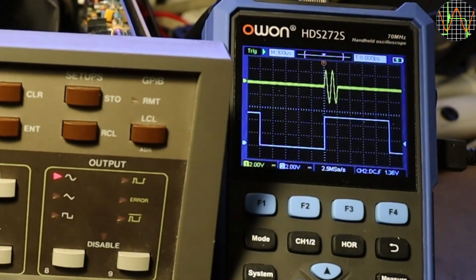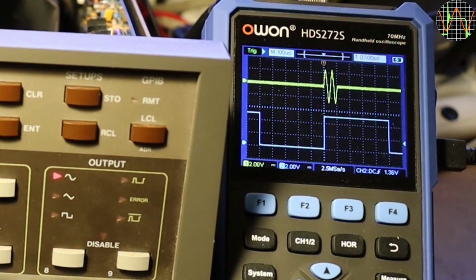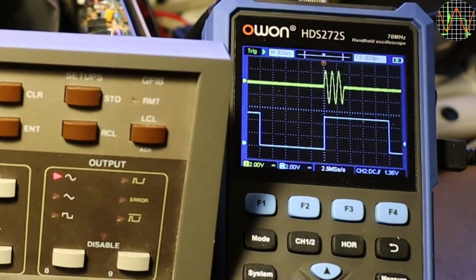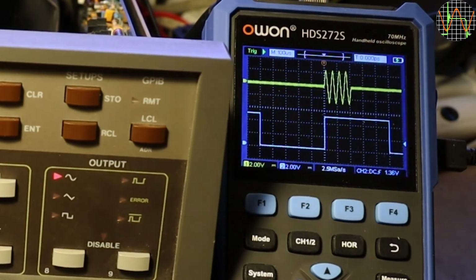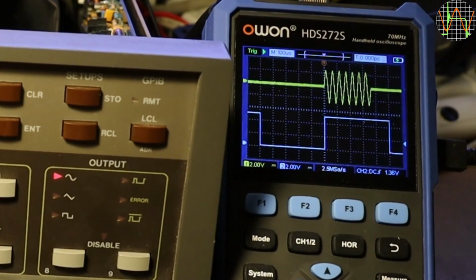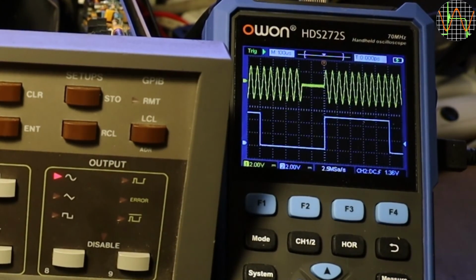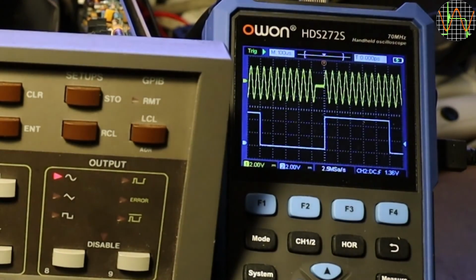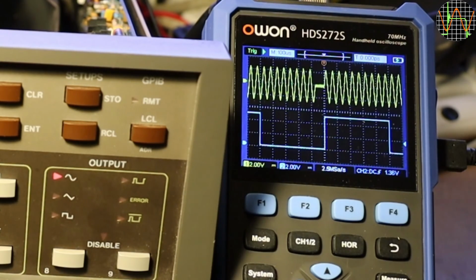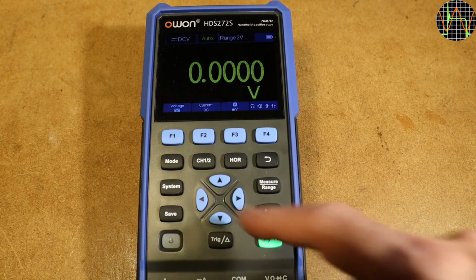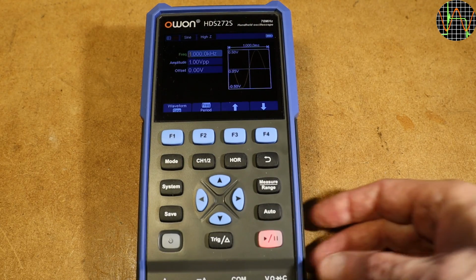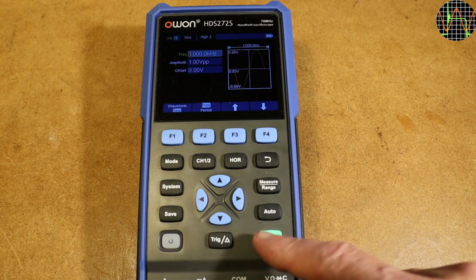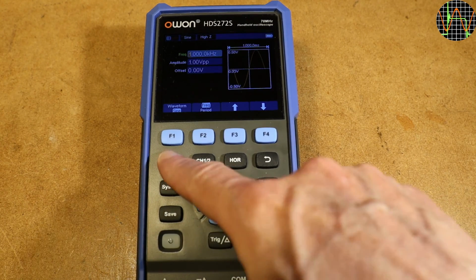The main purpose of the HDS272S is of course the scope. Overall I like it, but as with most instruments, it's important to learn about the quirks and limitations, and there are a few. Apart from the weird user interface, the most annoying one for me is the temperature sensitivity of the horizontal amplifier, requiring frequent auto-calibration cycles. Then there's sensitivity to electrical noise, making measurement of very low signals a challenge. Overall, I do not regret buying the HDS272S - it's the 3 most often used test devices rolled into one portable, battery-powered format.